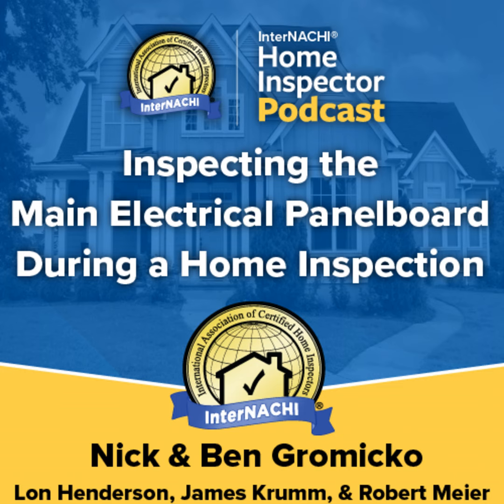Many manufacturers state that their devices should be tested by using the test and reset buttons on the breaker or receptacle. Electrical panel board inspection checklist. Take inspection images for every task of the inspection process. Wear personal safety protection, including glasses and gloves. Touch the panelboard cabinet and front cover with a non-contact voltage detector. Check for adequate workspace, clearances, and illumination at the panelboard.